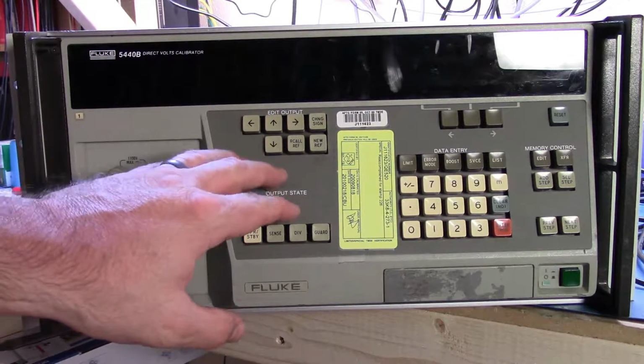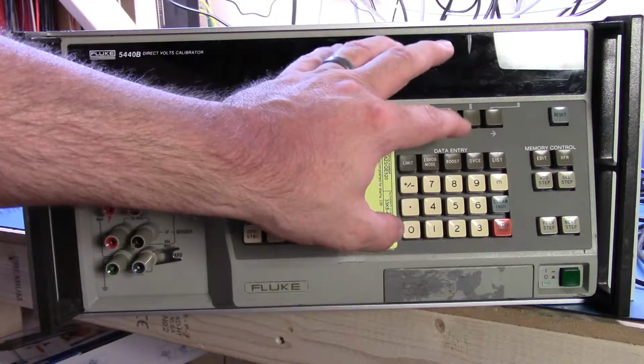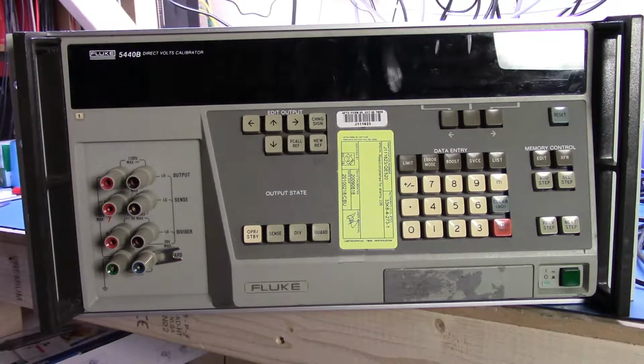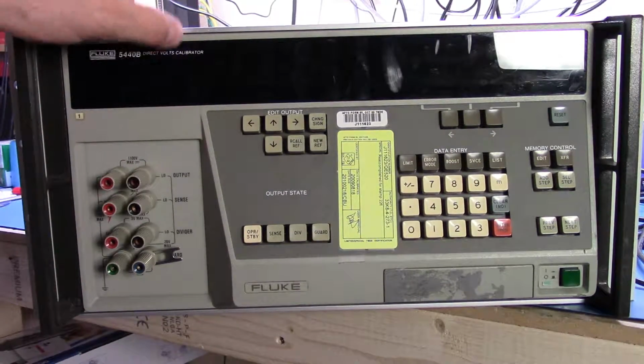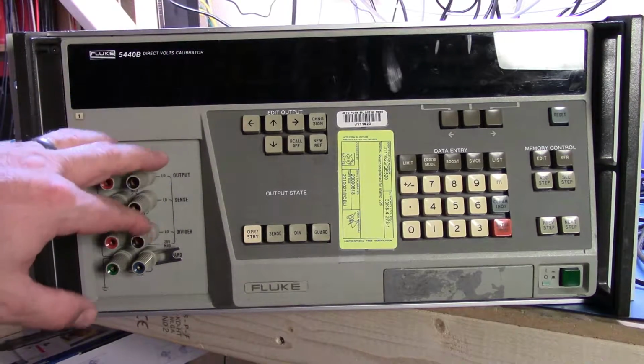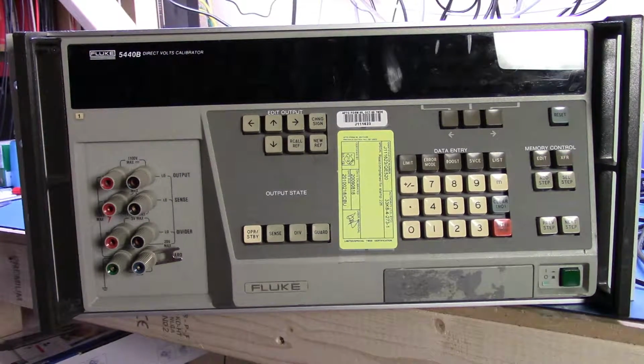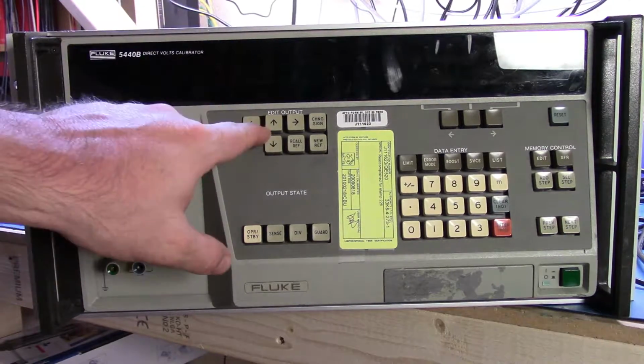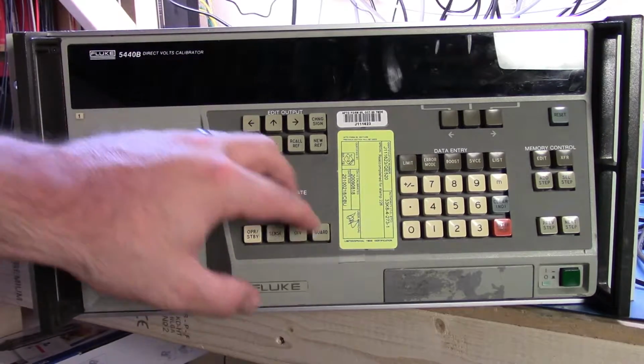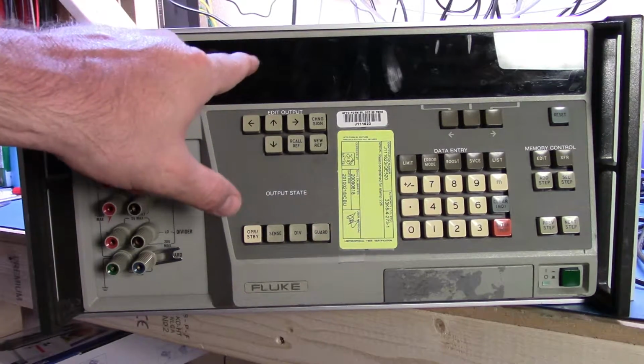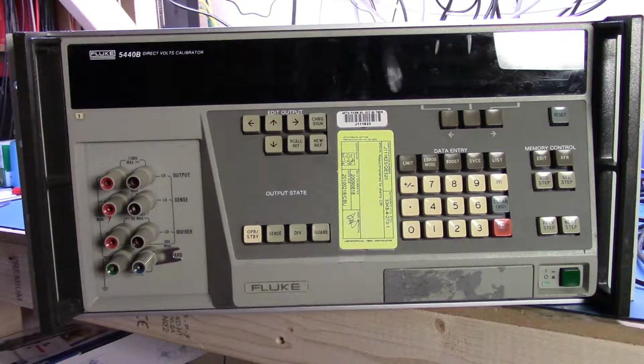I can put in all the ranges with the ppm values I should have as range plus digits, enter those into the calibrator, then connect the meter I want to calibrate straight to it. Then I use these controls to bring the display back to the value I've set.